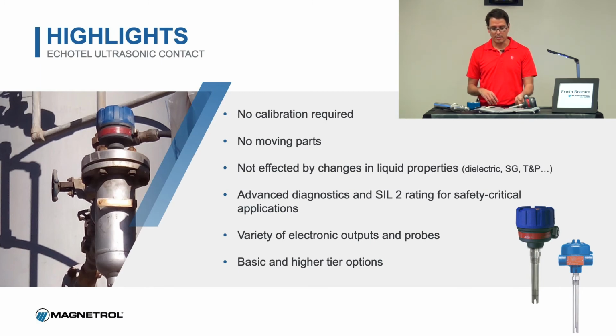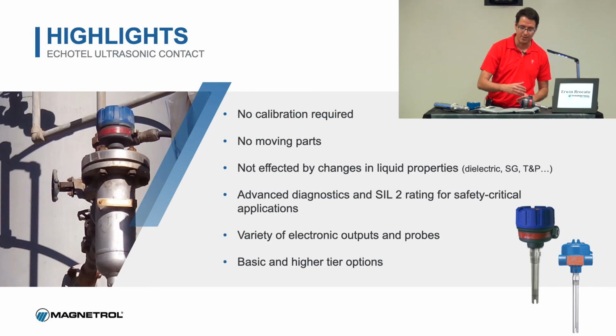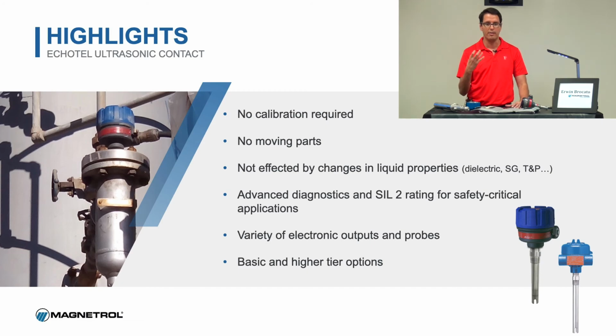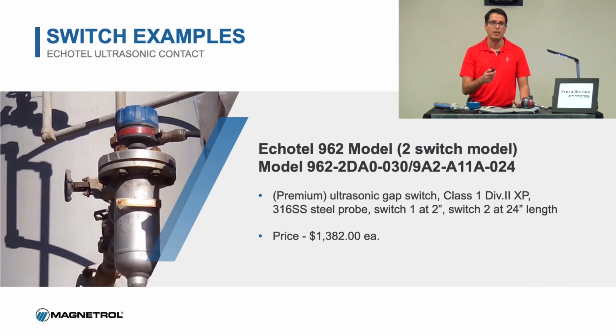Now, I do want to talk about limitations before we go to price points. One of the limitations with this device: if you have a very viscous product, it's going to accumulate in the sensor, and then eventually there's going to be so much accumulation in there that it's going to think it's a level. So I do not recommend this product for highly viscous products, like molasses or honey or a very, very thick crude or anything like that. You do not want to use this product because it will not work correctly.